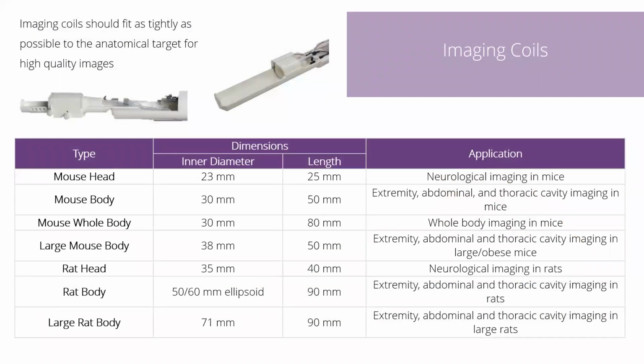When choosing the system, it's really important that we consider, again, your anatomical targets. When operating at 1 Tesla, it's really important that we get the imaging coil as close to the anatomical target as possible. So for that reason, we have a number of different coils that we would choose from. The mouse head coil allows for the coil to sit very tightly towards the head, and you can see here that it's actually integrated into the nose cone. For the body coil, you would position the animal and simply slide the body coil over top, choosing the diameter that would best fit the mouse that you're imaging.